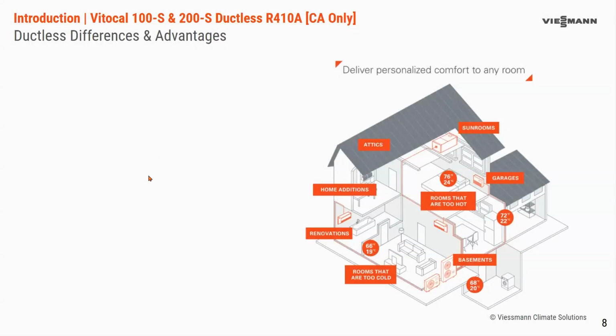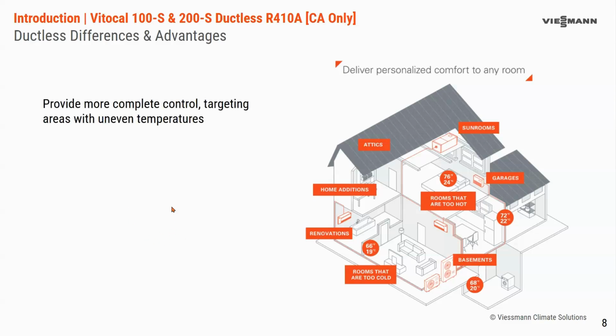So a little bit more on the ductless advantages. This image here is used in our marketing. It's a good representation of what challenges ductless can help with. You provide more consistent comfort with a ductless system with an air-to-air inverter heat pump, as it's able to maintain a temperature rather than overshoot or undershoot like a 2-stage or single stage on and off operation. So you're able to have more consistent comfort. The installation is oftentimes less invasive than a complete new ductwork or central ducted system. So there's less labor, less materials, and often a shorter installation time with these ductless units.